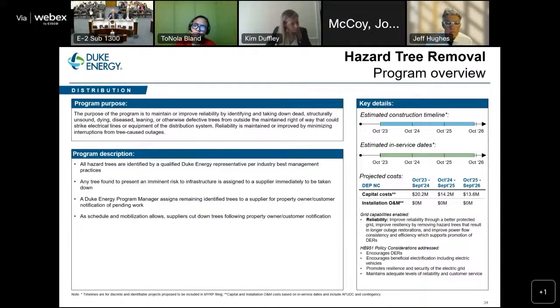Vegetation within the rights of way typically is smaller vegetation, limbs falling, et cetera. Many times it doesn't actually damage our facilities, it just causes an outage. But at most, it typically would just break the wire. You have a tree falling from outside the right of way — it is not only going to take the wire down, it likely is breaking a pole or multiple poles that now have to be replaced. So we have infrastructure replacement to do before we can even begin restoration in those cases.